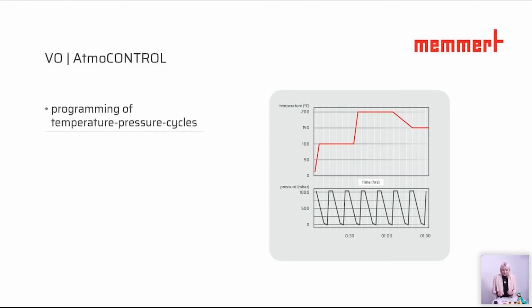This means it is a highly precise vacuum setting, and that is really for applications where you need a very fast drying process, because by setting high and low pressures, you can speed up the drying process. So that means this is for very special professional uses, to go ahead with the Memmert vacuum oven with this digitally controlled pressure in the ramp operation.